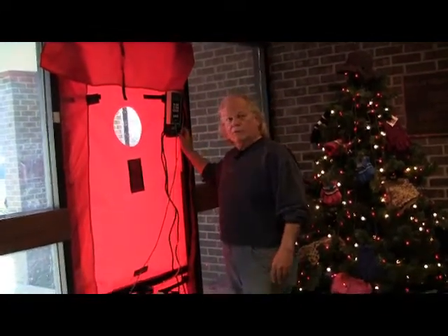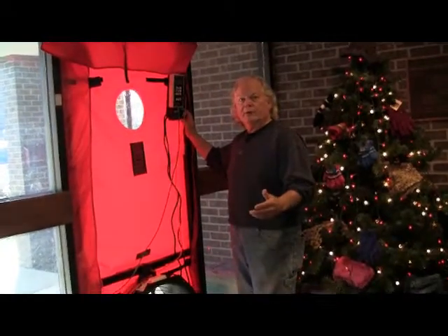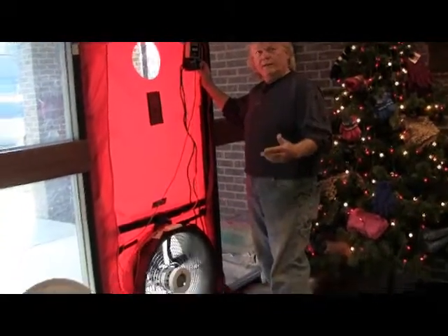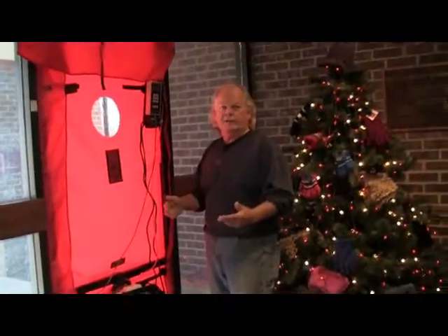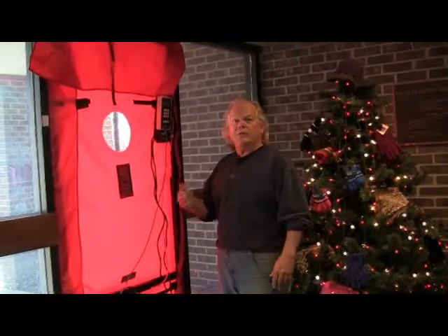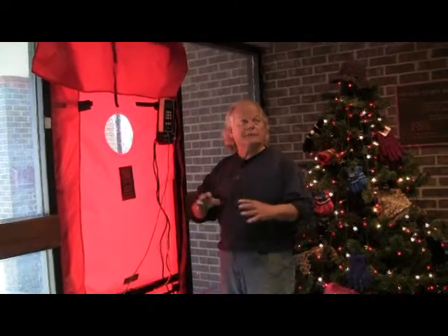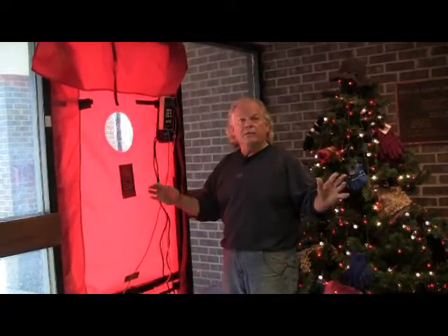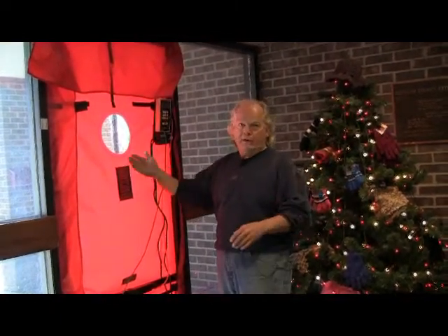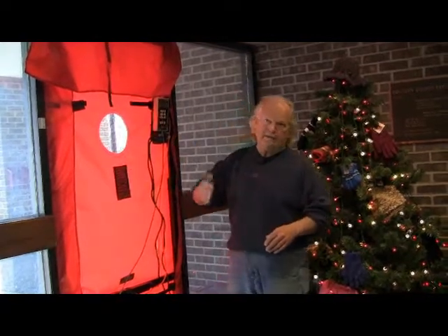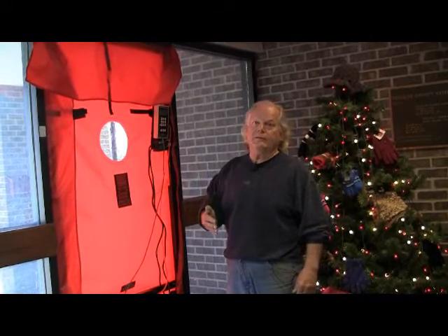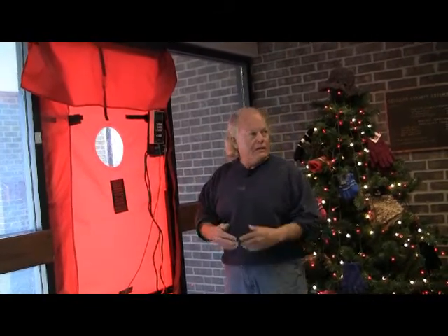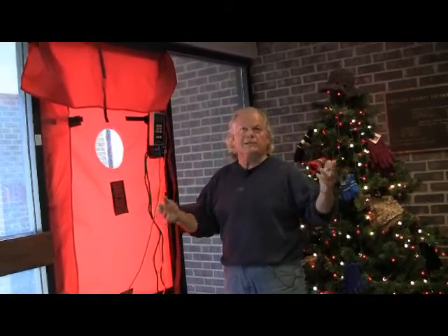We've done another blower door test with all of the registers taped off and calculated the amount of leakage we have and did the math necessary to understand the air changes per hour. We found that with all of the registers taped off and the ducting systems isolated, we've dropped from 0.81 air changes an hour to 0.56 air changes per hour. Mathematically, that turns out to be almost 30% of the leakage in this building can be attributed to leaks in the ducting system.